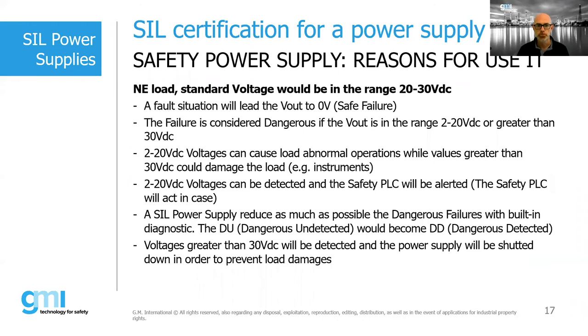Why is it important to use a separate power supply system? First of all, we know that the standard voltage for a normally energized load is in the 20-30 volt DC range. As we have seen previously, conditions that lead to a power supply output voltage between 2 and 20 volt and higher than 30 volt are considered dangerous failures, which negatively affect the application. A separate power supply significantly reduces undetected dangerous faults thanks to a built-in diagnostic system. In fact, if an anomalous output condition is detected by the separate power supply diagnostic, it brings the output to 0 volt, which represents the safe fault condition.